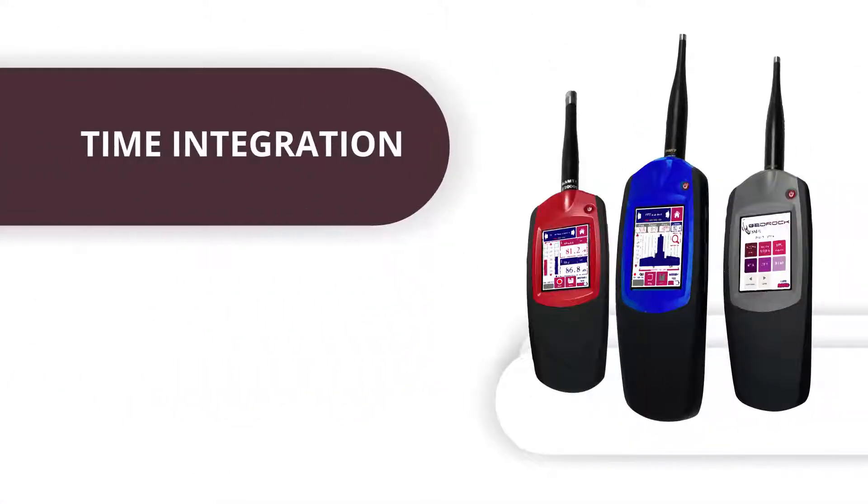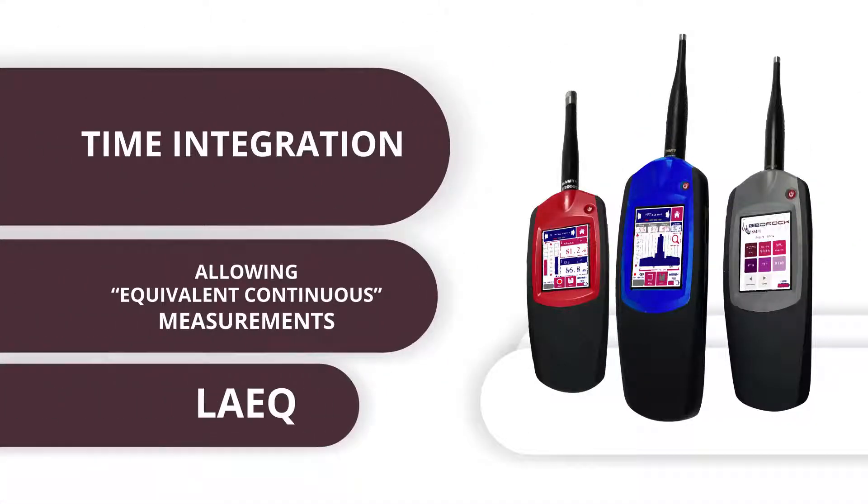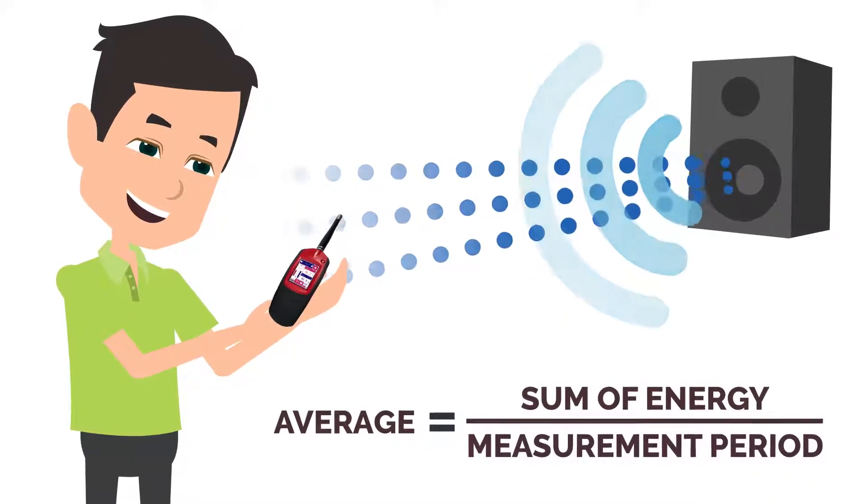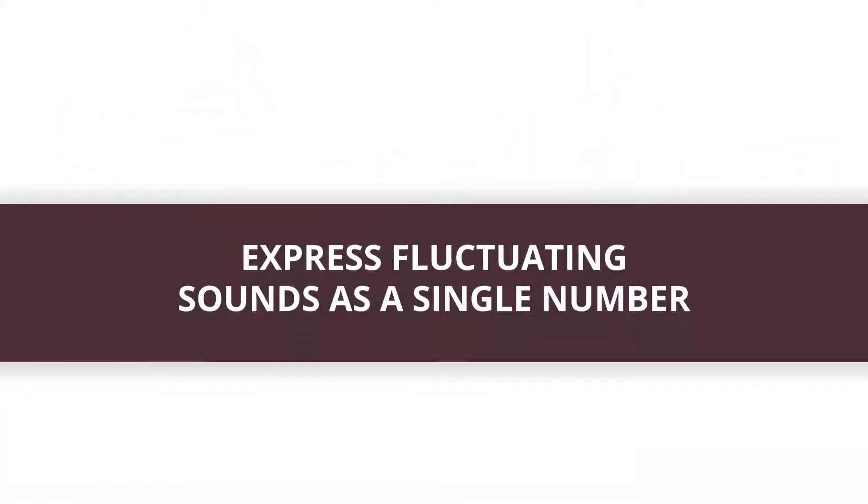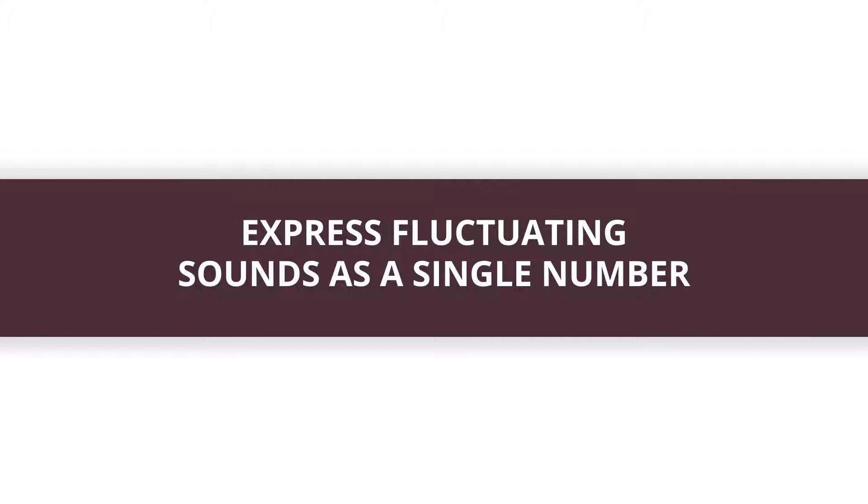The Bedrock meters also support time integration, allowing equivalent continuous measurements such as LAeq. All the energy detected during the measurement is then summed up and averaged over the measurement period. This is a way to express fluctuating sounds as a single number.